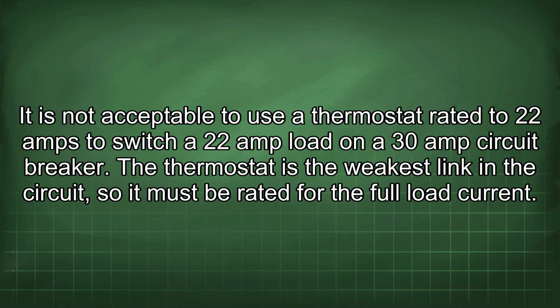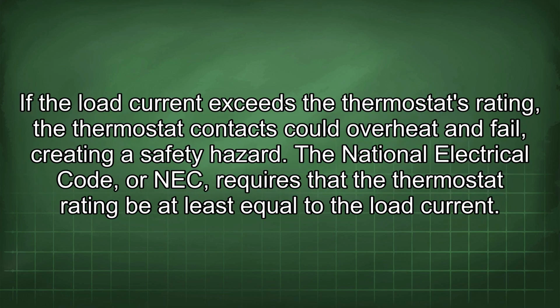It is not acceptable to use a thermostat rated to 22 amps to switch a 22 amp load on a 30 amp circuit breaker. The thermostat is the weakest link in the circuit, so it must be rated for the full load current.